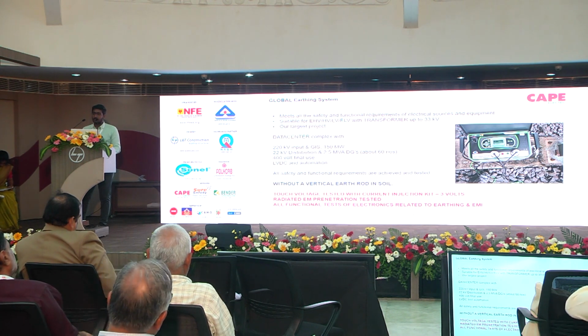And a 400 volt final use at the consumer premise and LVDC and automation areas. So this will ensure the safety parameters for the complete building, not only for the building but from the incoming to the end use area also, the complete earthing safety requirements in accordance with standards will be ensured. While adopting this kind of system, there is no need of any additional vertical electrodes in the soil. The touch voltage current injection kit test will be at 3 volt, radiated electromagnetic penetration will be tested, and all functional tests of electronics related to earthing and EMI area.